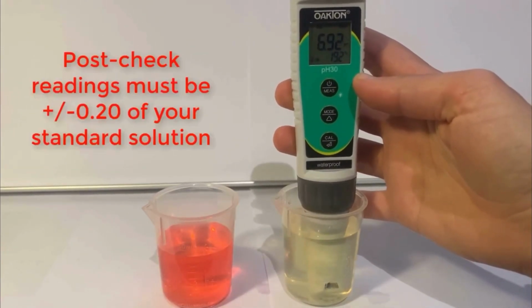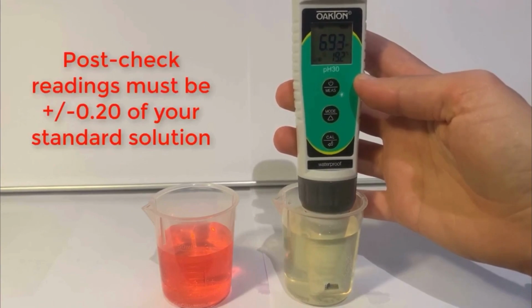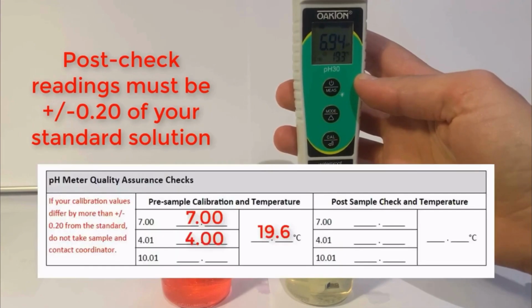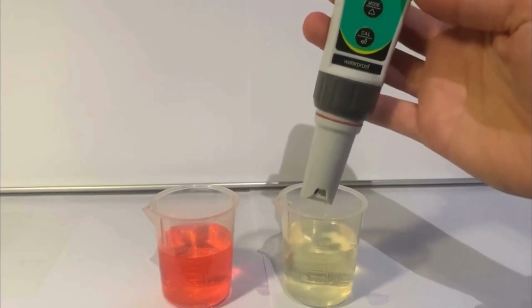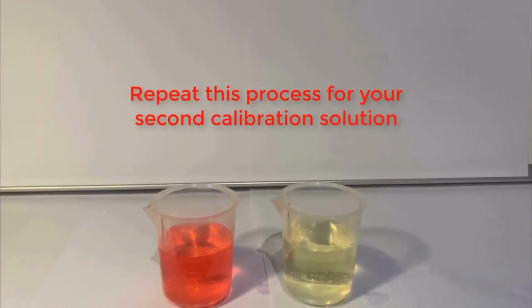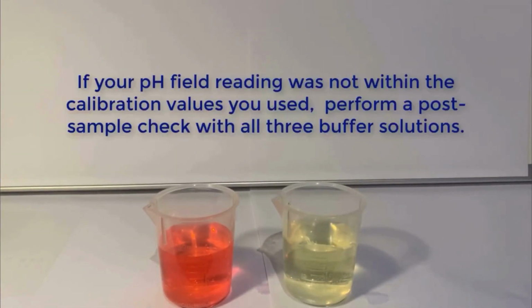This number must be within 2/10 of your standard solution, so with buffer 7, this needs to be between 6.8 and 7.2. If your reading is outside of this range, contact your coordinator for help resolving the issue. Repeat this exact same process for your second calibration solution. If your pH field reading was not within the calibration values that you used, perform a post-sample check with all 3 buffer solutions.